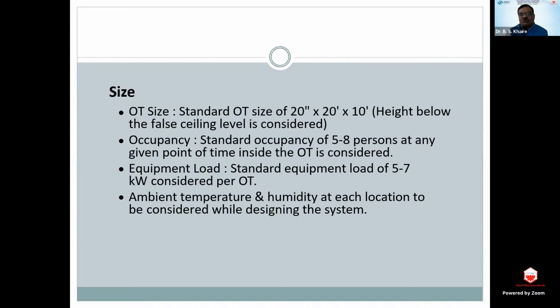The equipment load will be around 5 to 7 kilowatts considered per operation theatre, and ambient temperature and humidity at each location are to be considered while designing the system.